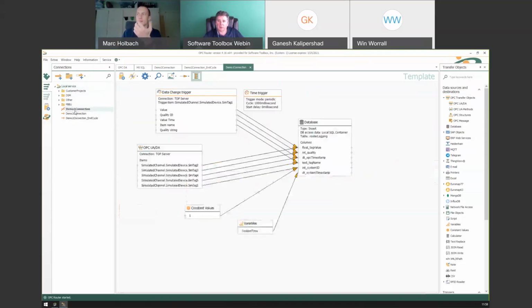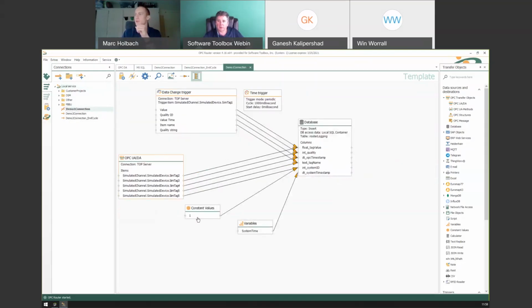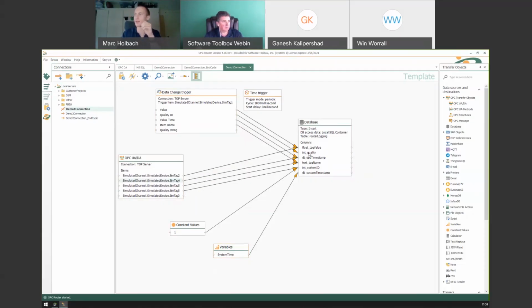And if we were to jump back to our first demo connection, which is much uglier now than it was initially, these connections are read only. We're not writing back to the OPC server at that point. From a security standpoint, it is one-directional communication. If I now wanted to make one of these write connections, I would need to draw the arrow into the OPC server. So the direction of the arrows does matter in whether a component is written to or read from.